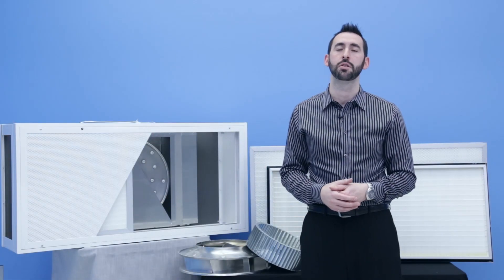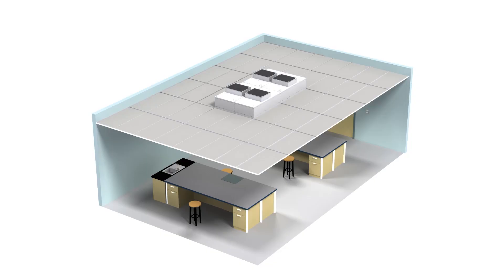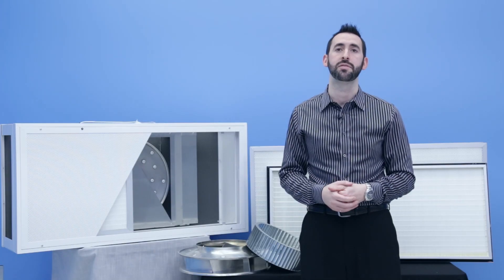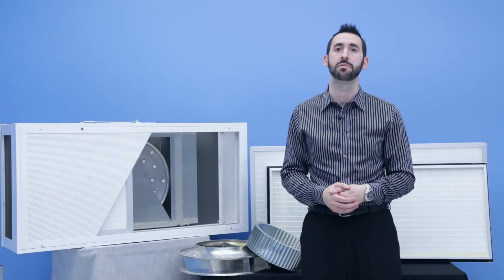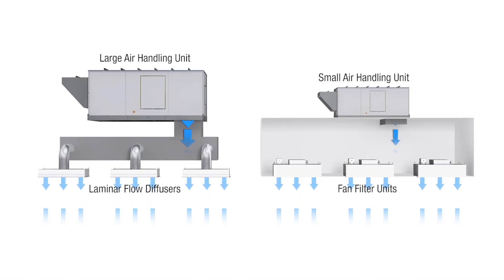FFUs can also be used to quickly and easily upgrade the ISO classification of rooms simply by adding fan filter units to the ceiling. It is common for ISO class 1-5 clean rooms for the entire ceiling to be covered in fan filter units. By using FFUs instead of a central air handler to provide the required air changes, the size of the air handler can be greatly reduced.